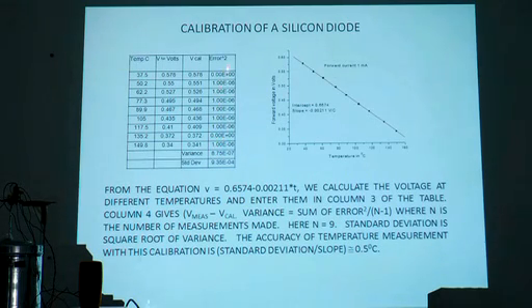You add all these error squares, you divide it by n minus 1, where n is the total number of calibration points, that is n is 9, so you divide it by 8, that is the variance. You take the square root, that is the standard deviation. It is 0.9 millivolts. 2.1 millivolt corresponds to 1 degree. 0.9 millivolt will correspond to 0.45 degrees. So, if you measure temperature with this silicon diode, the error in temperature measurement will be plus or minus 0.45 degrees centigrade.